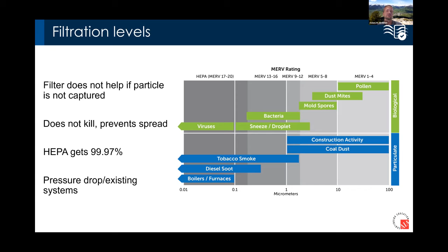We hear a lot about HEPA filters. The HEPA filter was actually invented for nuclear fallout shelters during the Cold War, so it was intended to filter out radiation. That's a very, very small thing that is likely overkill for what we're trying to do here. Healthcare settings do use HEPA. If there is a heightened concern, you can certainly, in a new construction or new air handling unit, design to be able to use a HEPA filter, but those filters are very small, so that fan has to work really, really hard to push the air through all those small holes. So sometimes with these existing systems, there's only a certain level of MERV rating that we can achieve.